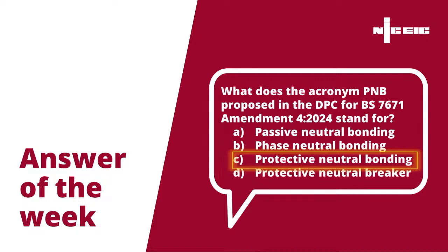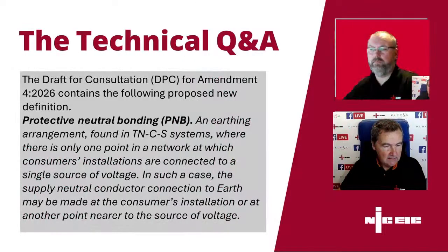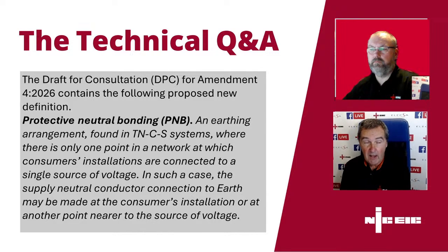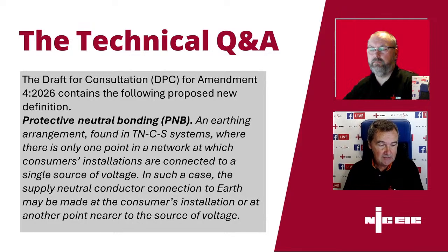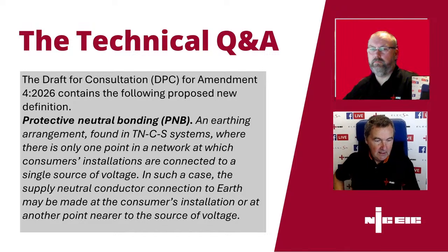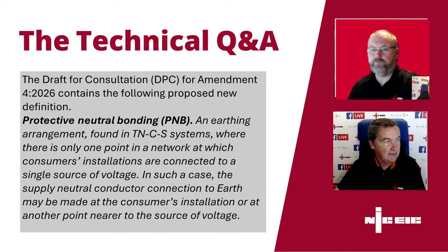If we have a quick look, there's a new definition proposed for Amendment 4 2026, where protective neutral bonding is an earthing arrangement found in a TNCS system where there's only one point in the network at which consumer installations are connected to a single source of voltage. In such a case, the supply neutral conductor connected to earth may be made at the consumer's installation or at another point near the source of voltage. So as the definition says, similar to TNCS in that there's a combined protective and neutral conductor in the distribution element, but at some point there'll be a single connection to earth, which could be within the consumer's installation.